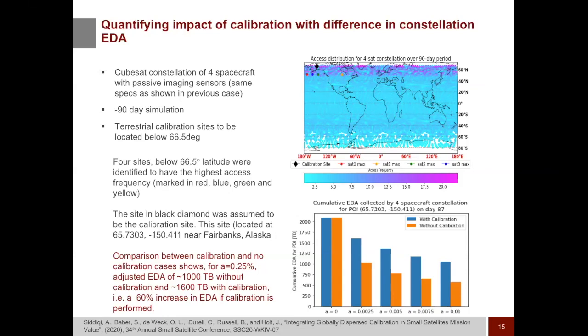We also run another case assuming no calibration happens, with data acquired by a sensor simply degrading over time at different rates. For this particular simulation and these assumptions, we find there's almost a 60% difference between the case with calibration and without calibration when A is 0.25%.